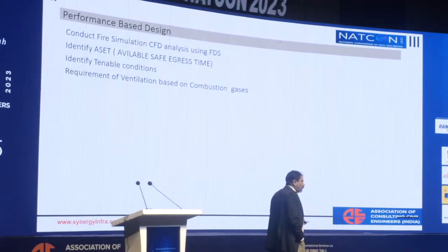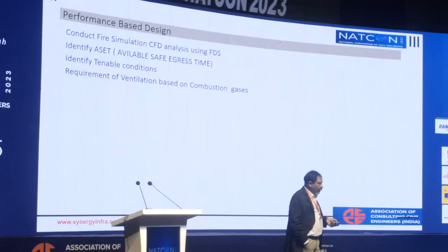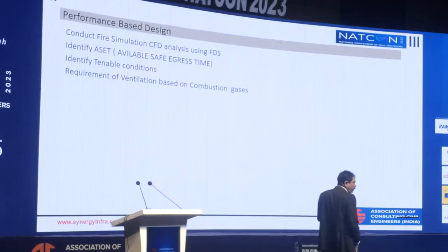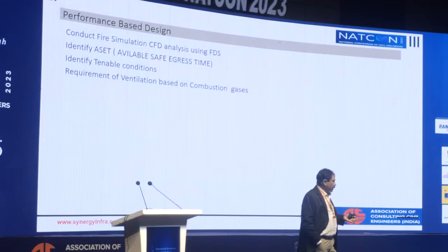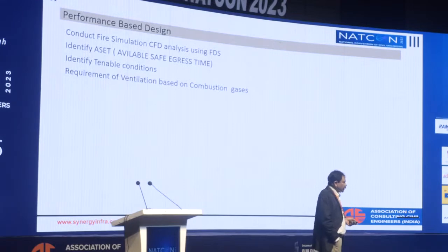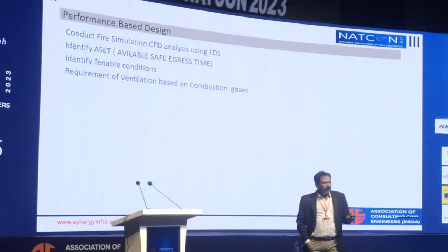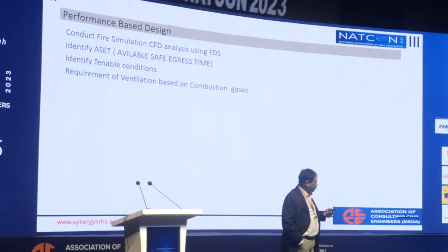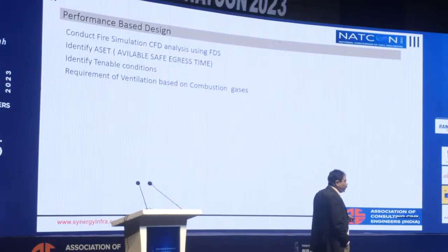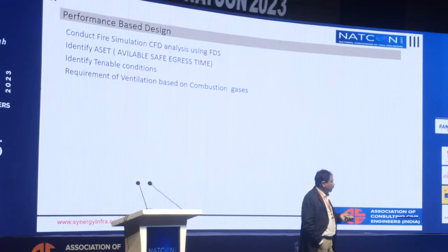Once that's done, we look at what should be the available safe egress time, meaning by how much time tenable conditions are maintained. Tenable conditions relate to three things: temperature, visibility, and toxicity. Unless these three are within limits, people may get affected. We have to consider toxicity from hydrogen sulfide, hydrochloric acid, and other gases generated due to the plastics used in buildings today, along with temperature rise, which can cause a lot of harm.